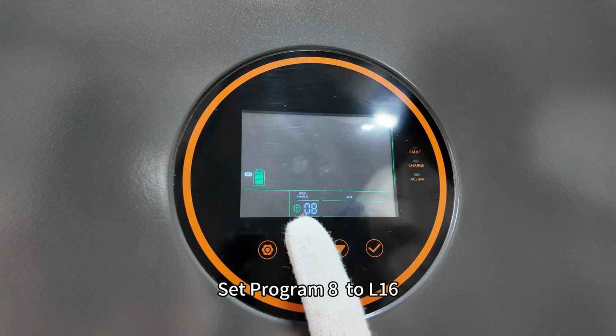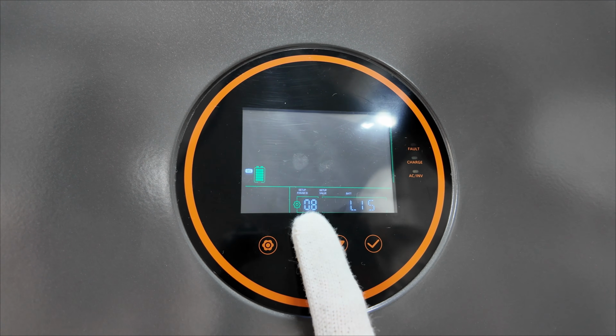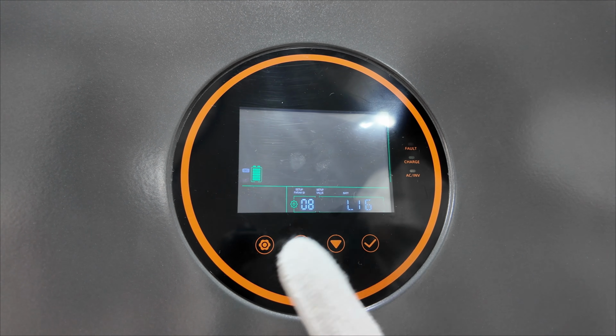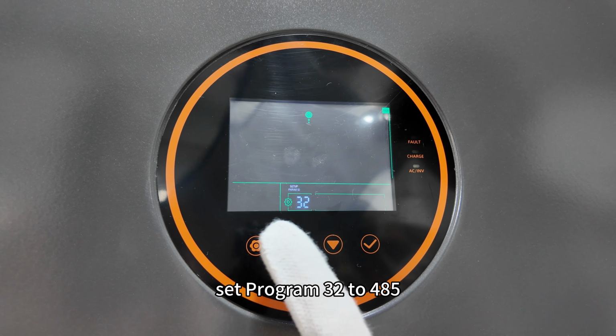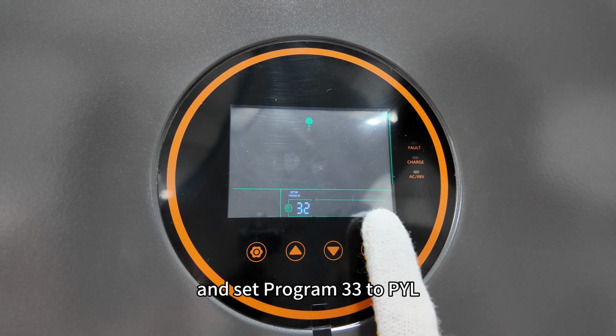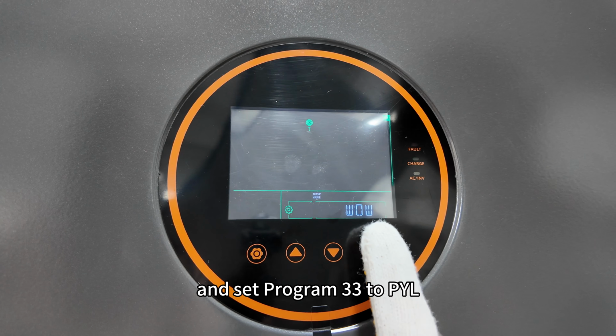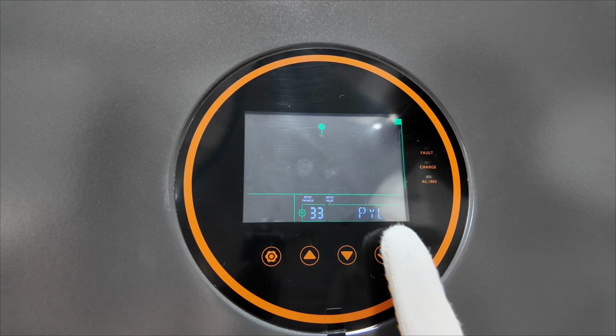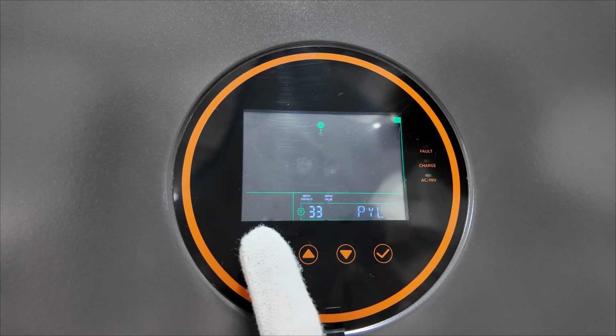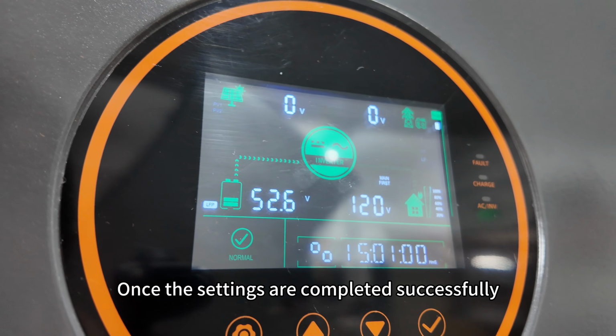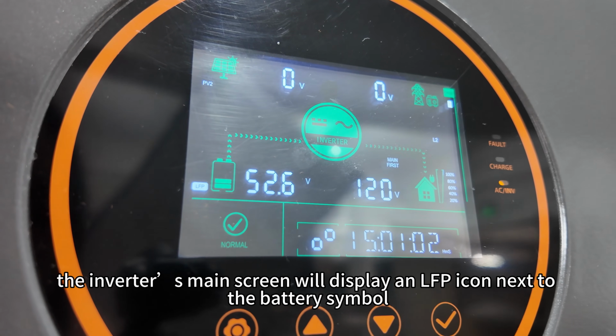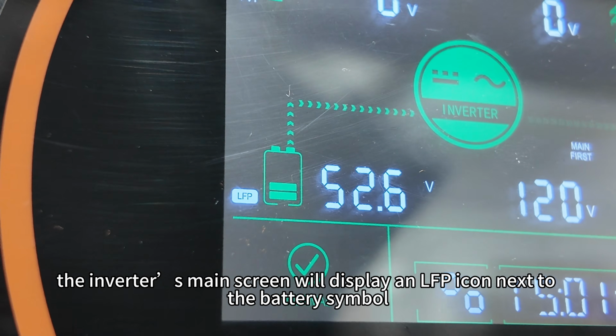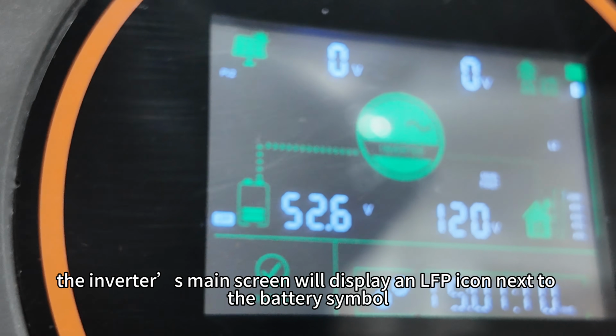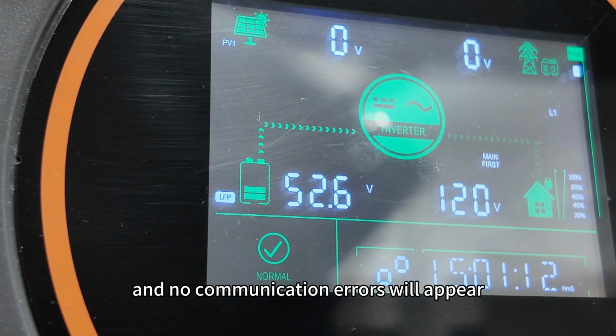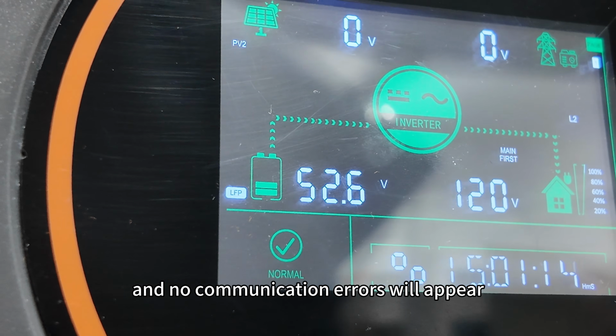Set program 8 to L16, set program 32 to 485, and set program 33 to PYL. Once the settings are complete successfully, the inverter's main screen will display an LFP icon next to the battery symbol, and no communication error will appear.